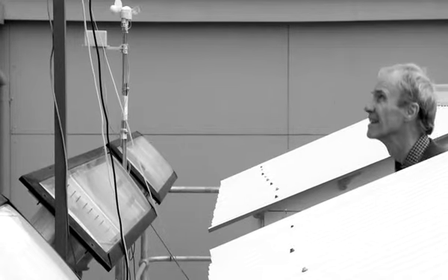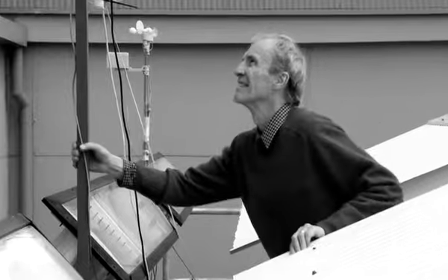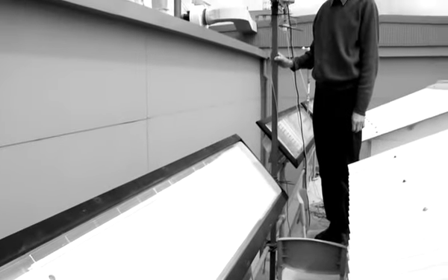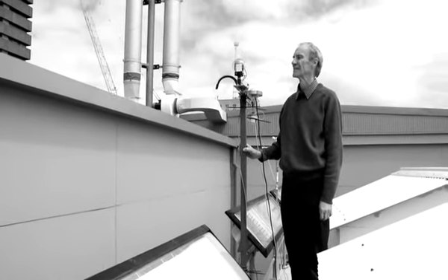And what are the factors that come into consideration there? In the building itself, we monitor the airflow and the temperatures. That's straightforward. But it's the outside, the environmental energy flows we monitor with the solar radiation, we monitor the atmospheric radiation, we monitor the wind speed, and we monitor humidity. And there's a variety of instruments needed to do that. The Weather Bureau does these things as well, of course, but we do them right where our building is, because it's very important to know what's happening at the building.